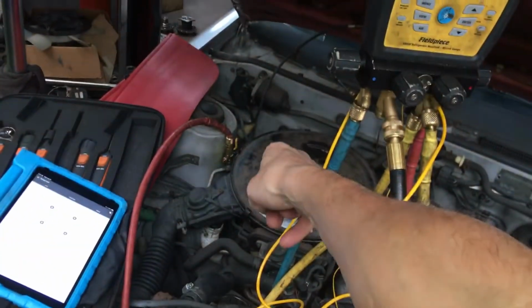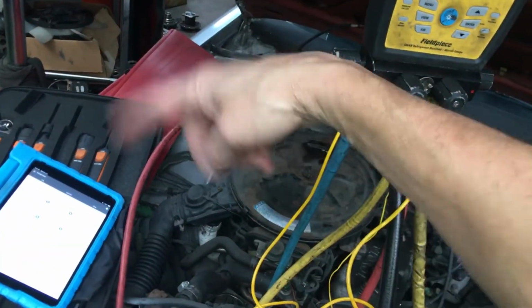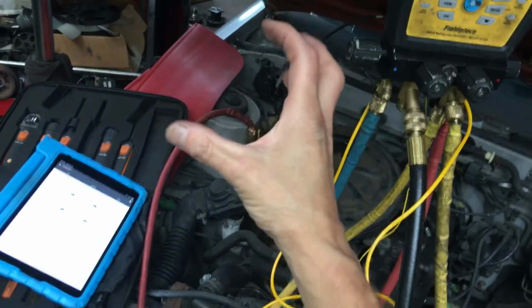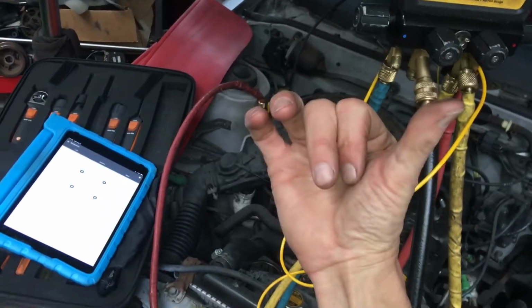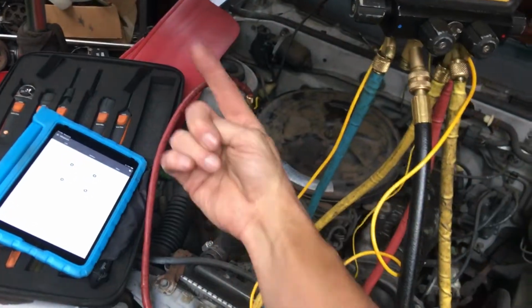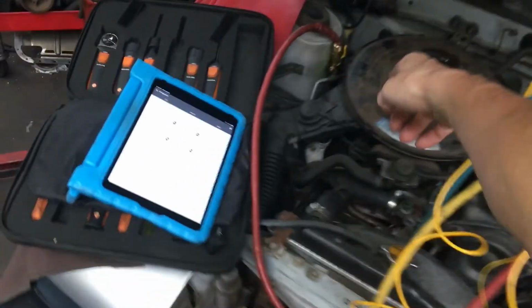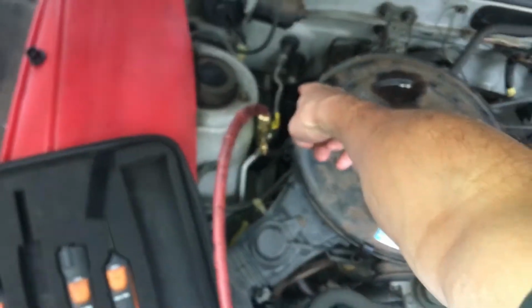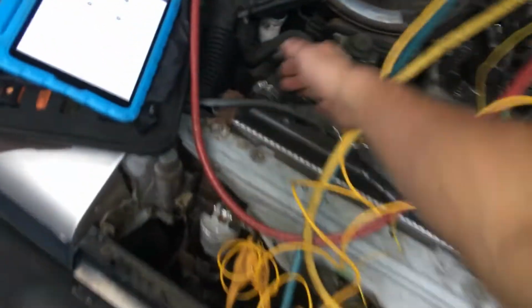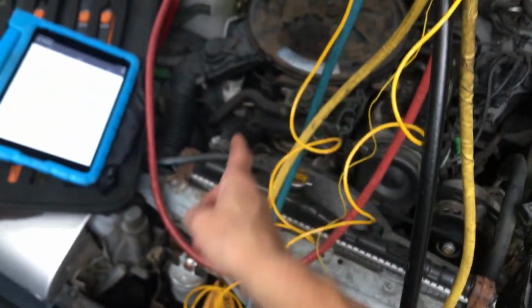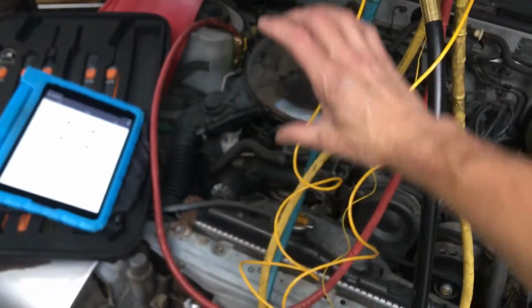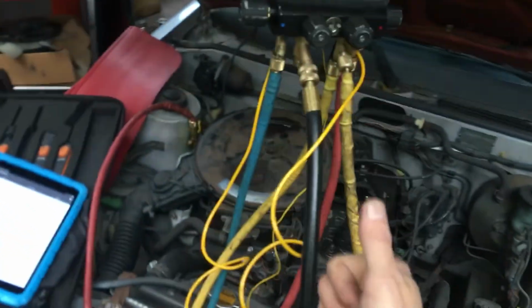By my probe being in the wrong location, you'd have to wrap insulation around it, put some shiny tin foil on it with the shiny reflecting out, because you have radiant heat coming up from the exhaust manifold when you hook up to the suction line coming out of the evaporator, and you have this really fast moving convection heat that is flowing over your probe, giving you wrong information.